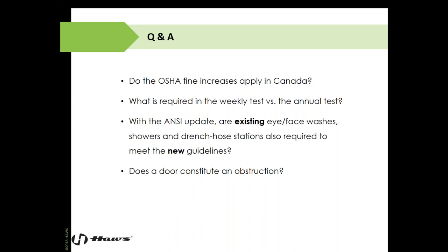And if you don't understand necessarily what a grandfather clause is, it's a clause that is included in the standard saying, hey, if you have equipment prior to the release of this, you don't have to comply with it. So if this has already been in place and you're compliant at the time, and then we release this, you're compliant. That is not the case with the ANSI standard. Whatever the current standard is, that's what we need to be complying with. So 2014 is the current version, everything I just went over, that's what's required.